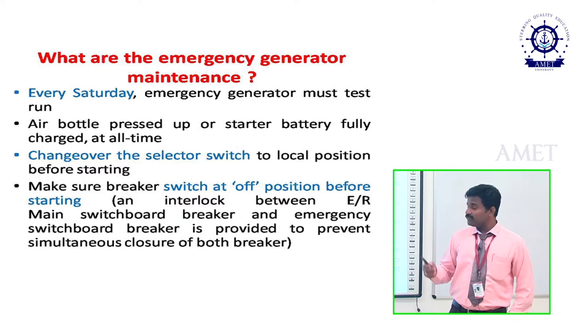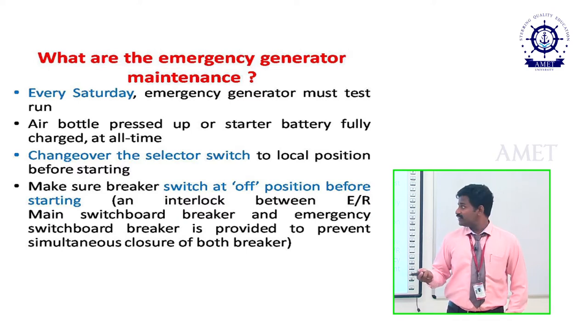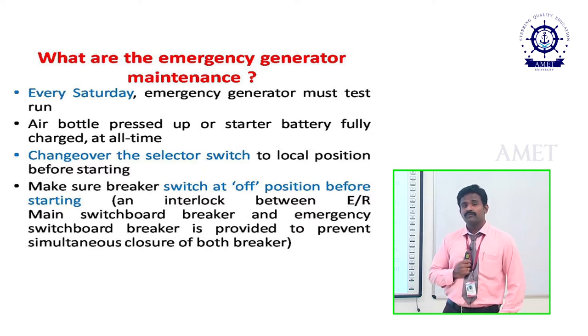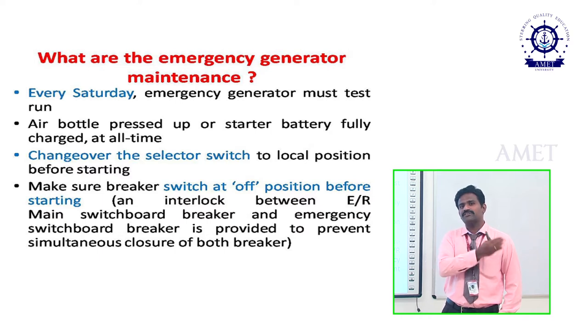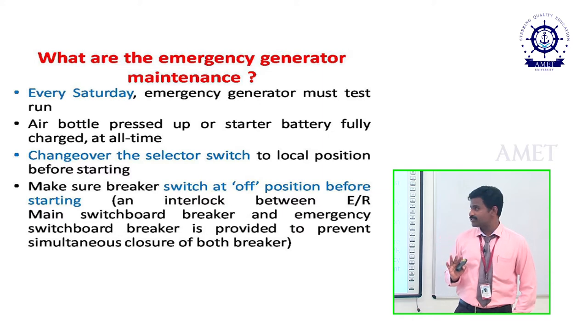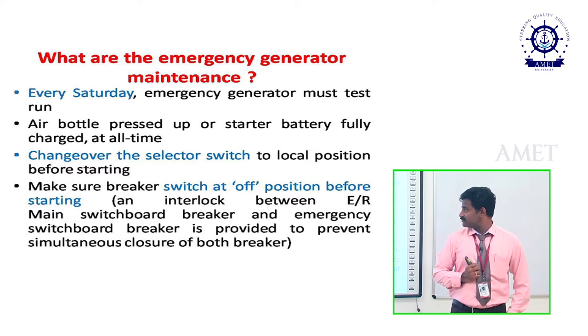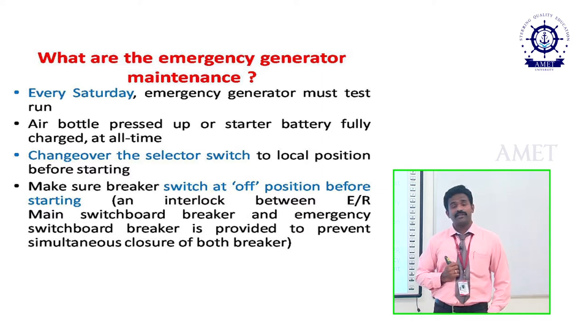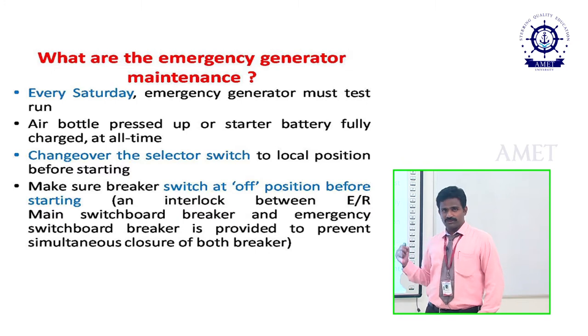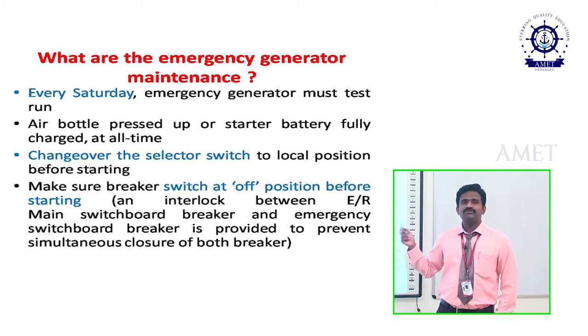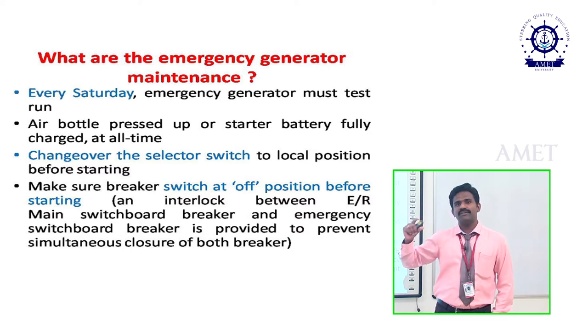Before testing the emergency generator, the air bottle pressure or starter battery must be fully charged at all times. Because one of the starting methods uses a battery, that battery must be fully charged. We also need to change the selector switch to the local position before starting. The changeover switch refers to the interlock switch between the main switchboard and the emergency switchboard.